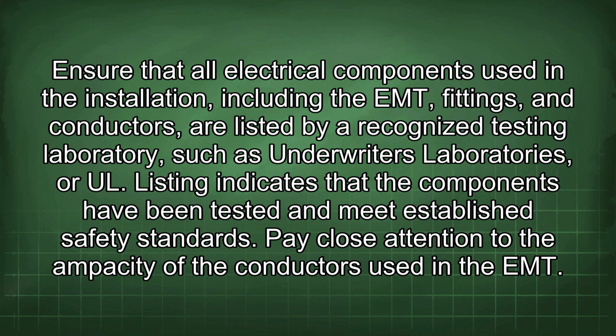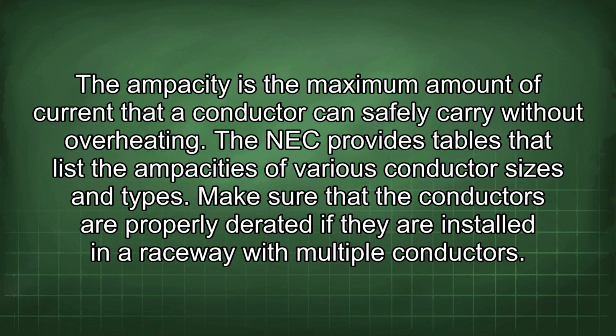Ensure that all electrical components used in the installation, including the EMT, fittings, and conductors, are listed by a recognized testing laboratory, such as Underwriters Laboratories or UL. Listing indicates that the components have been tested and meet established safety standards. Pay close attention to the ampacity of the conductors used in the EMT. The ampacity is the maximum amount of current that a conductor can safely carry without overheating. The NEC provides tables that list the ampacities of various conductor sizes and types.